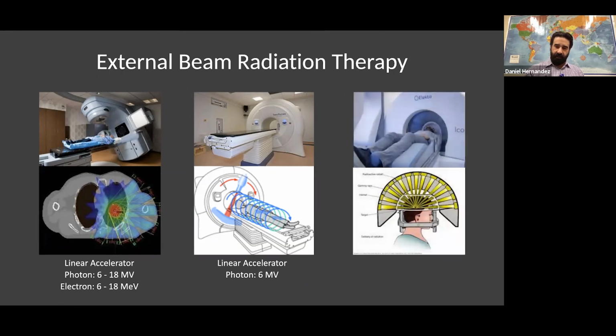And finally, by the way, each of these three types of machines are modalities that we had at our disposal at UC Davis while I was doing residency. So I got to become very familiar with each of these. This last machine is called an Elekta Icon, but rather than having a machine that produces the radiation, like the linear accelerators in the previous two photos, these are actually fixed radioactive cobalt sources, cobalt 60. And the energy itself is significantly lower at 1.25 MV.